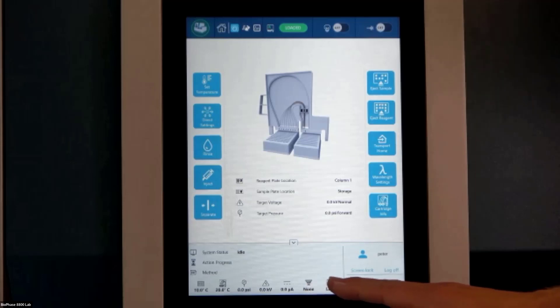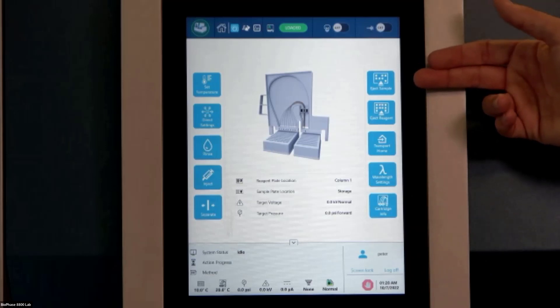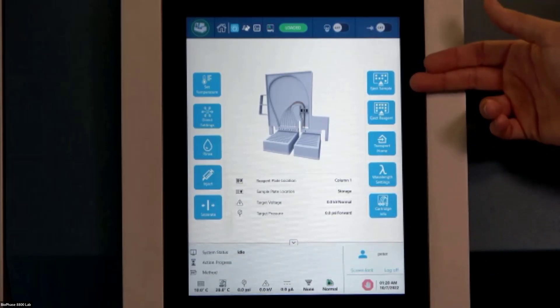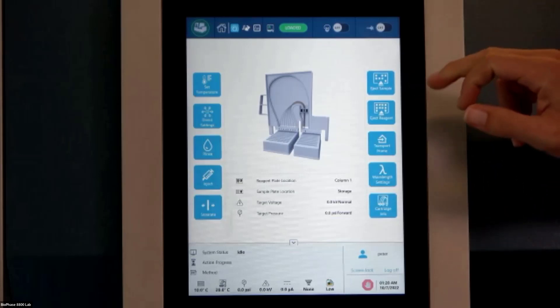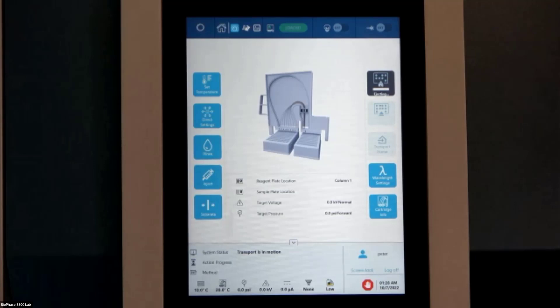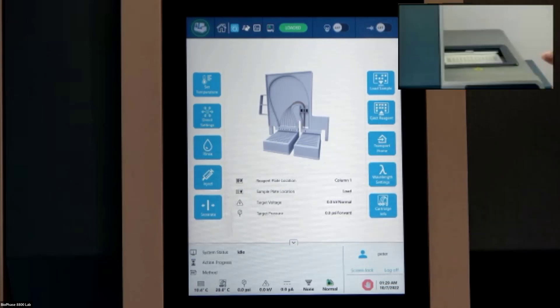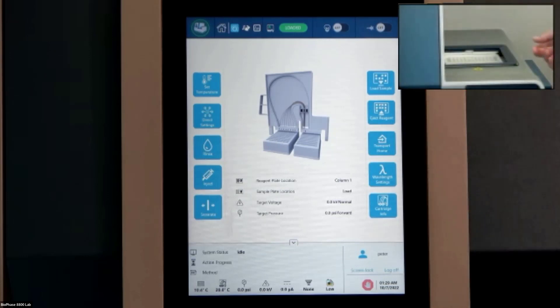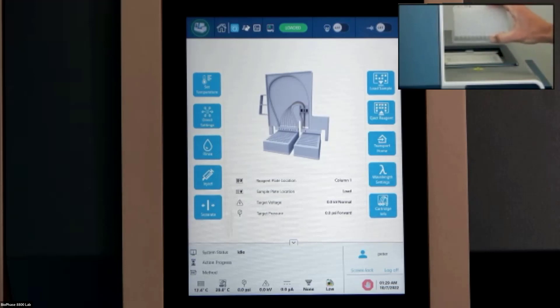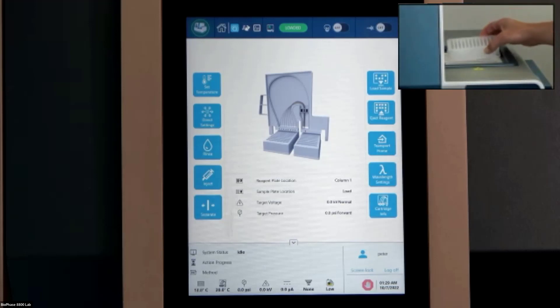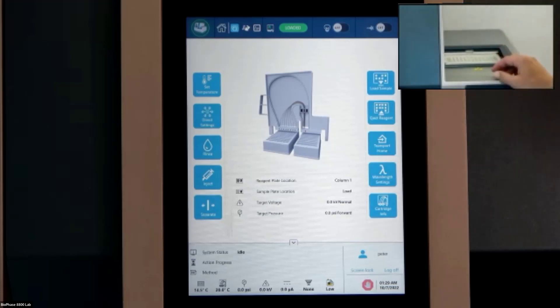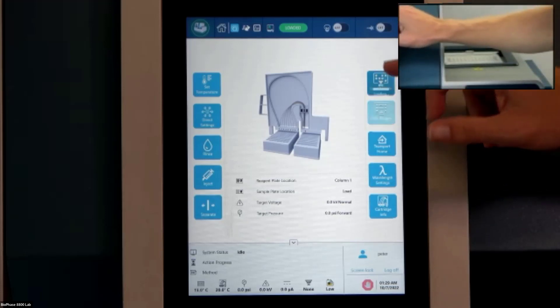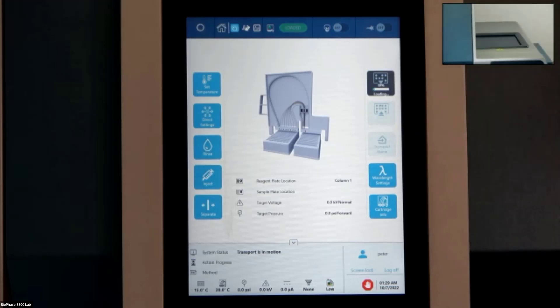Over here on the right side, we can see a few more icons. Here we have eject sample, eject reagent. If we click on that, we can see exactly where our reagents go. This tray cover opens up our 96-well reagent plates, our sample plate or reagent plate comes out. And then right behind it is our outlet plate that we saw in the software. Those just go in right there and we can choose to be either the reagent plate or the sample plate. And then once we have them in there, we just click load. And then we see that the tray closed up.